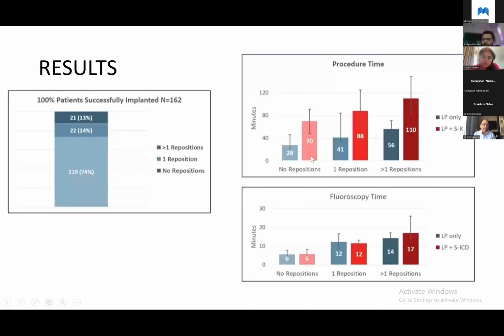When there was no repositioning required, the procedure time was defined for the leadless pacing system from sheath in to sheath out, and for subcutaneous ICD implantation from first incision to the last suture. So when there was no repositioning, the procedure time was 28 minutes for the leadless pacemaker.